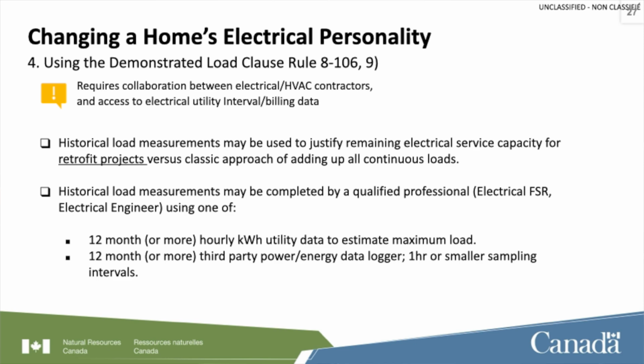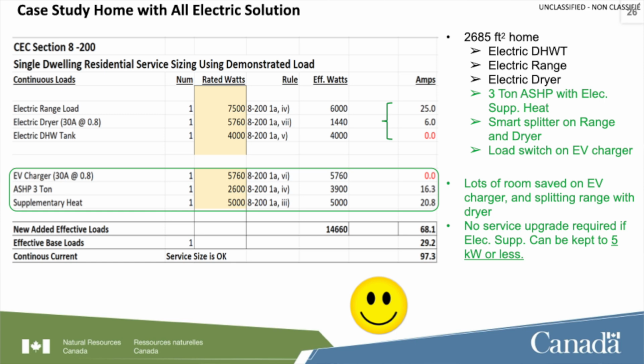Just a comment about that electric heat, probably not right, that number. Because we're seeing, you're looking at that 20 amp, I would be surprised. That's only about 5,000 watts supplementary heat system. Yeah, which 20 amps makes sense for the sizing, because keep in mind, when we're running this supplementary heating system, that 5,000 watts is running in addition to the air source heat pump. They run at the same time, so you're getting heat from both.